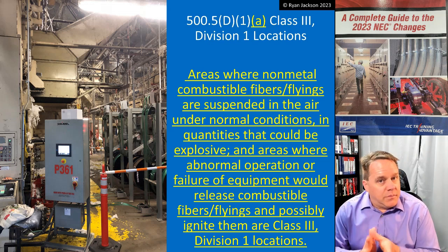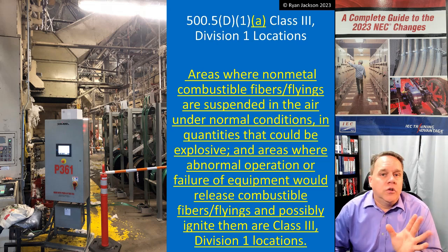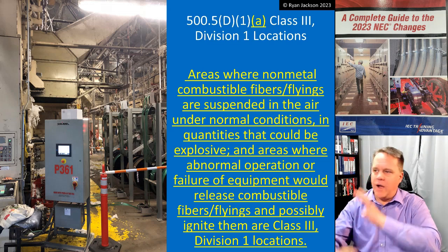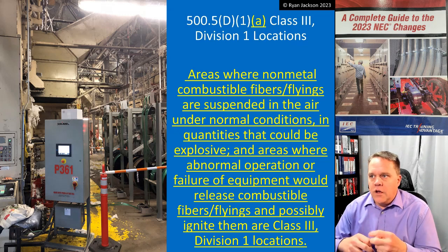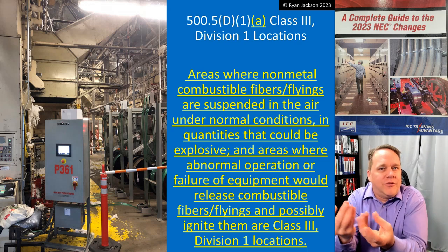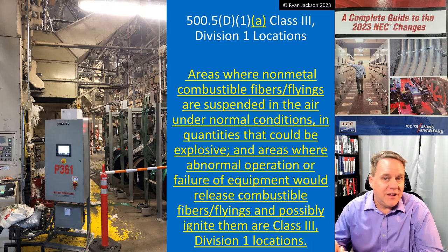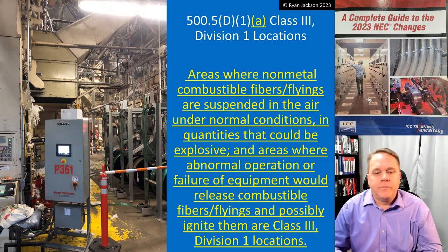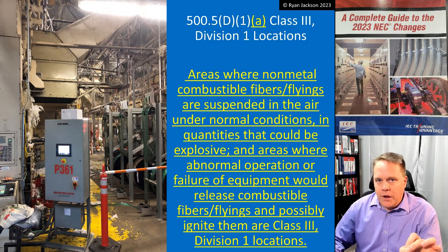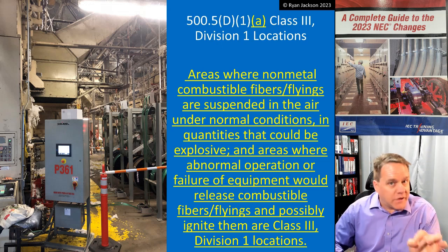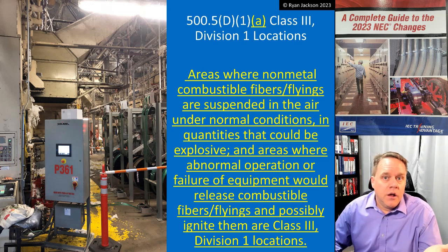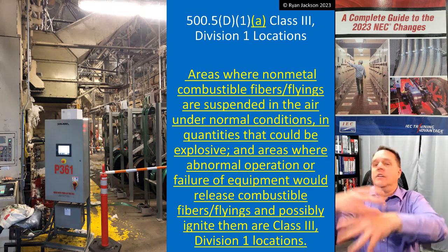Non-metal combustible fibers or flyings suspended in the air under normal conditions in quantities that could be explosive — that's what defines this classification. Even when really producing wood fibers on a lathe, it's wood in large pieces; it could be ignited but it's not going to explode. In the photograph shown, a factory processing cotton — fine, wispy cotton boll material all over the place under normal conditions — that probably is a Class 3 Division 1.